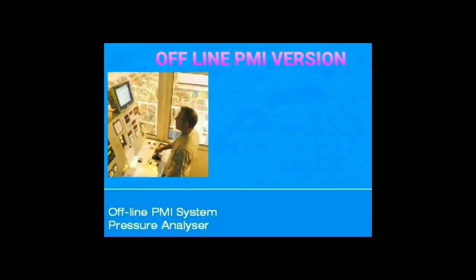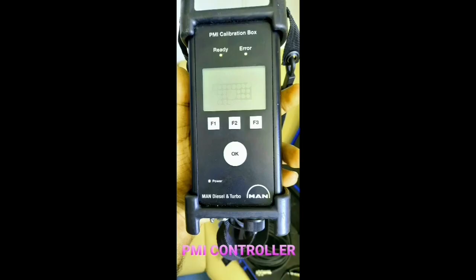The second one is the offline PMI version. In this system there is a high-performance piezoelectric transducer which needs to be mounted manually on the cylinder head indicator cocks from which the cylinder pressure is measured. The transducer has to be manually moved from one cylinder to another between each set of measurements.